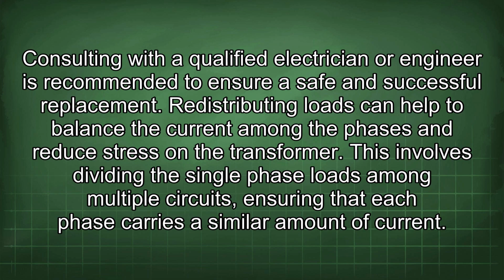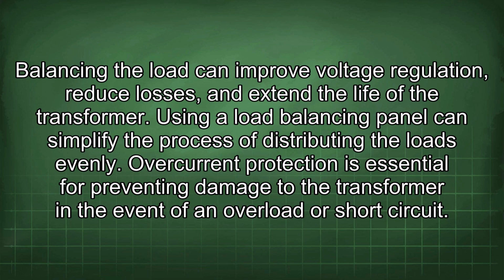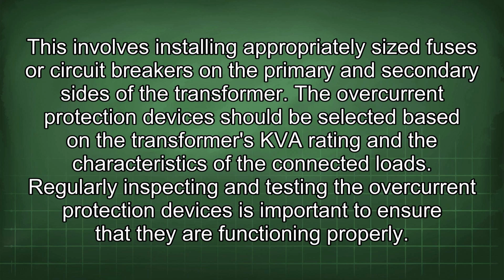Redistributing loads can help to balance the current among the phases and reduce stress on the transformer. This involves dividing the single-phase loads among multiple circuits, ensuring that each phase carries a similar amount of current. Balancing the load can improve voltage regulation, reduce losses, and extend the life of the transformer. Using a load balancing panel can simplify the process of distributing the loads evenly. Overcurrent protection is essential for preventing damage to the transformer in the event of an overload or short circuit. This involves installing appropriately sized fuses or circuit breakers on the primary and secondary sides of the transformer. The overcurrent protection devices should be selected based on the transformer's kVA rating and the characteristics of the connected loads. Regularly inspecting and testing the overcurrent protection devices is important to ensure that they are functioning properly.